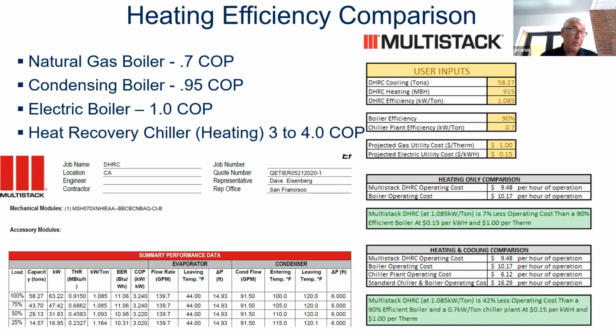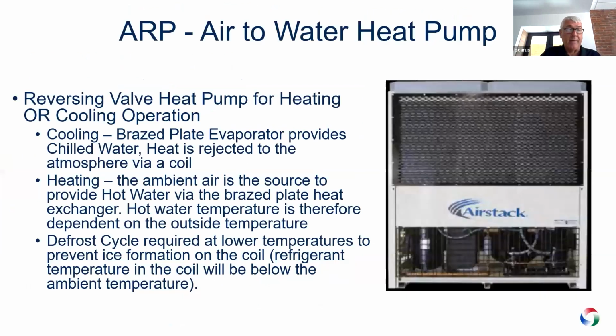COPs anywhere up to, actually, I've seen them as high as right around 7 COP for a heat recovery chiller. So the proof is kind of in the pudding and in this spreadsheet. And the Long guys all have this at their disposal if you want to now give it a test drive yourself. Going over to the air side of the equation, we've been doing this particular type of machine for about 10 to 12 years now.